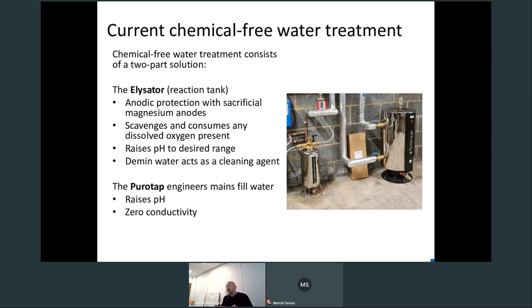What then follows through is you have demin water that's in that system. That acts as a natural cleaning agent, and that agitates and puts into suspension the sludge, slurry, and the fixed debris around that system, carries it round to the reaction tank, the Elysator, ready to be blown down in the ppms. And then what we have is we have the demineralizing unit, which is the Purotap, and this engineers the mains fill water, and this sits between the cold mains inlet and the pressurization unit, and this engineers the raw fill water coming in, raises the pH and gives a zero conductivity going into that system.